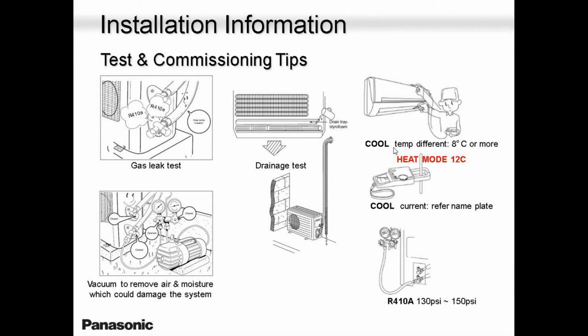Gas leak test, pressurize the system. Don't over pressurize it, please. I have issues of guys over pressurizing the system, 450, 500, and then guess what? They push the valve in, and Freon gets leaked out, R410 leaks out, and then what?